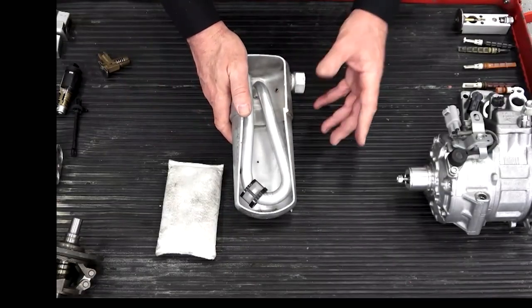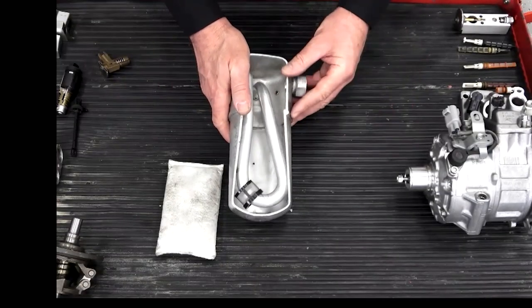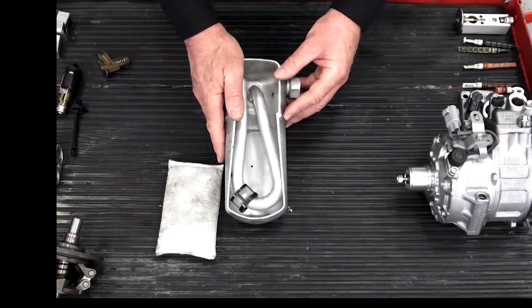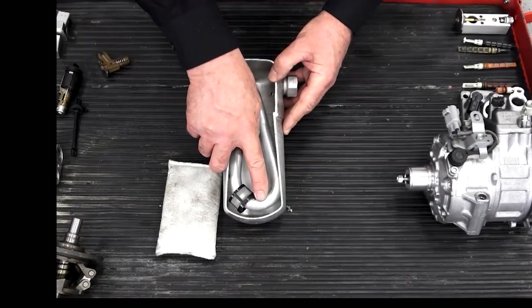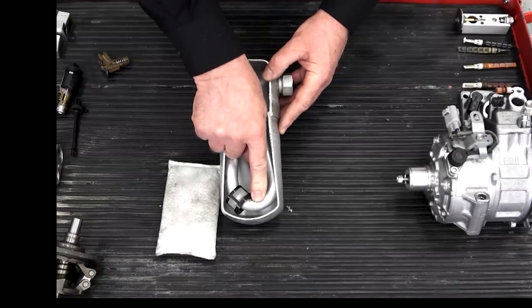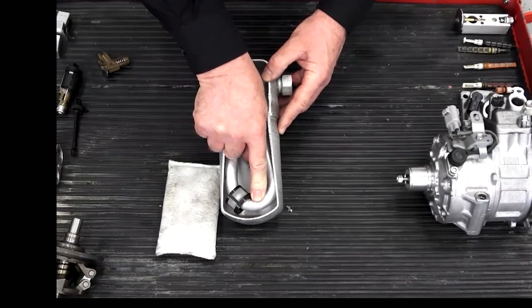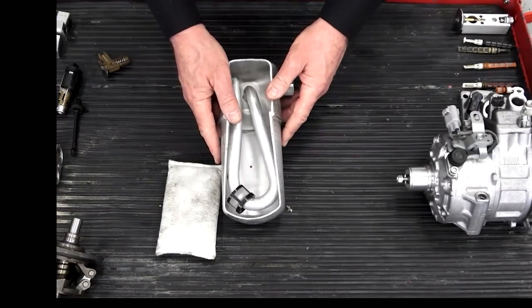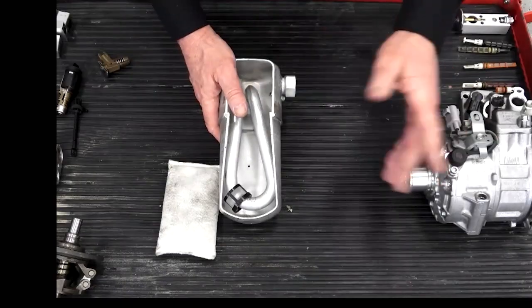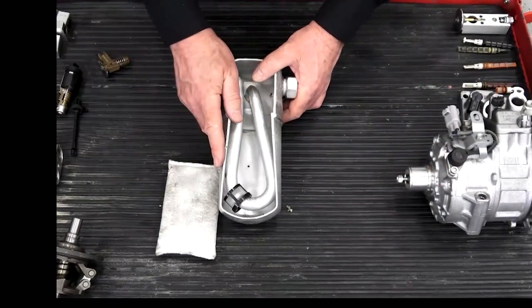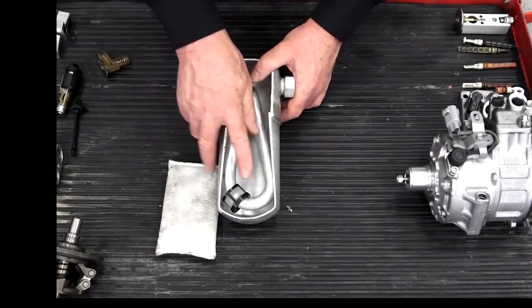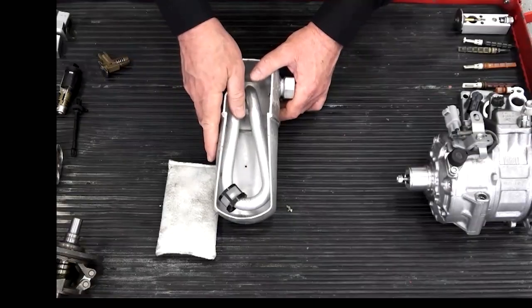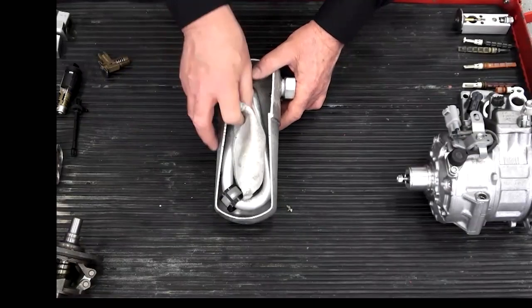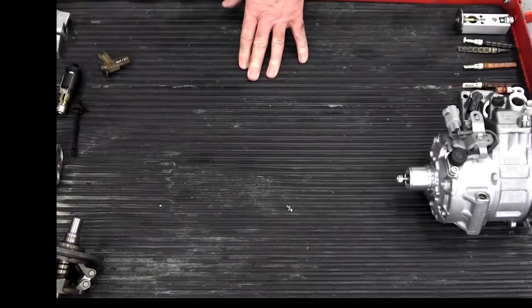And that's because every molecule of the refrigerant gets to evaporate inside the evaporator. But if there is no liquid covering the bottom of that J tube, the compressor will seize. It'll go out the shop blowing ice cold air, but it'll come back to you in days or weeks or months, depending on how low it is, with the seized compressor because it's not getting any lubrication. So that's the function of the accumulator.